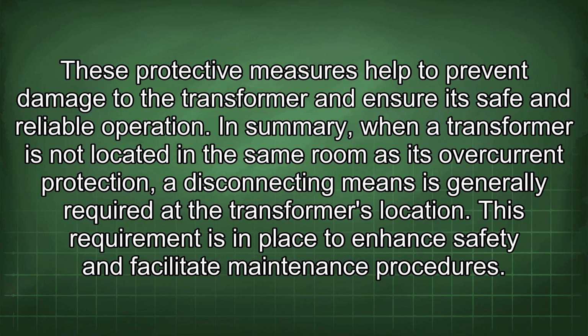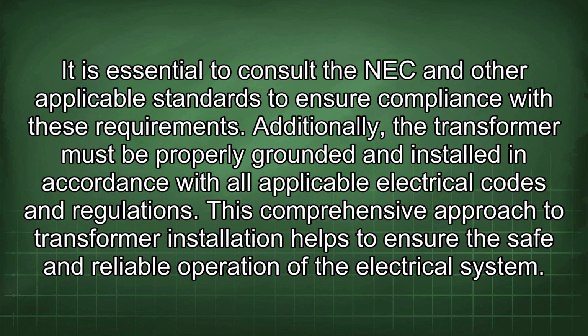operation. In summary, when a transformer is not located in the same room as its overcurrent protection, a disconnecting means is generally required at the transformer's location. This requirement is in place to enhance safety and facilitate maintenance procedures. It is essential to consult the NEC and other applicable standards to ensure compliance with these requirements. Additionally, the transformer must be properly grounded and installed in accordance with all applicable electrical codes and regulations.